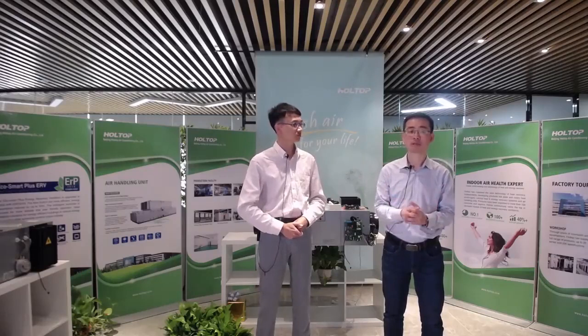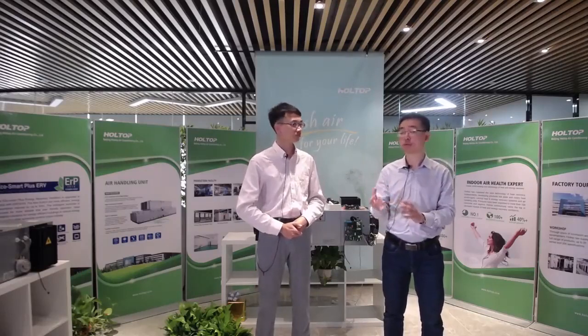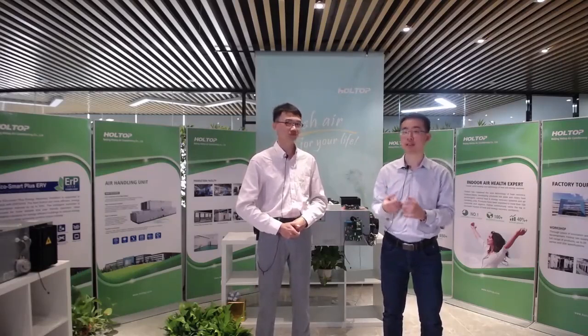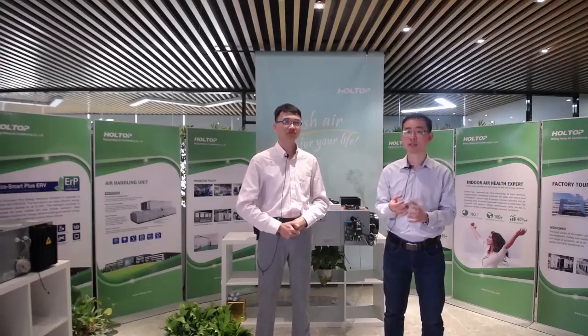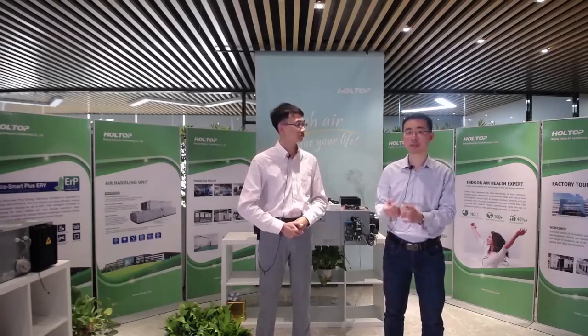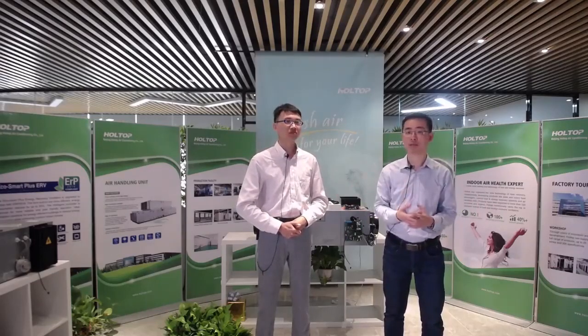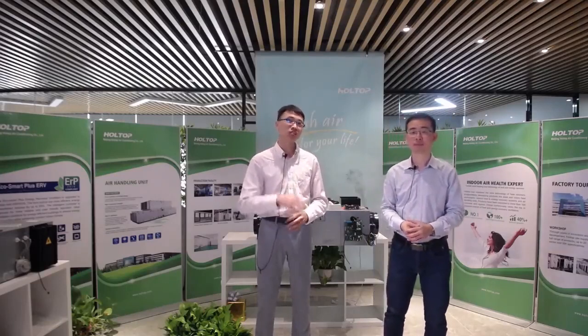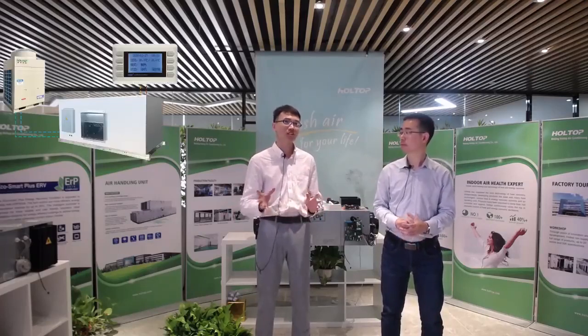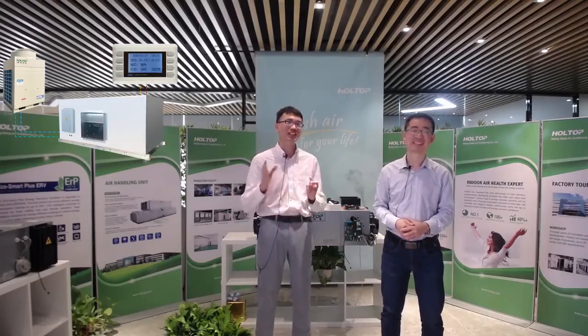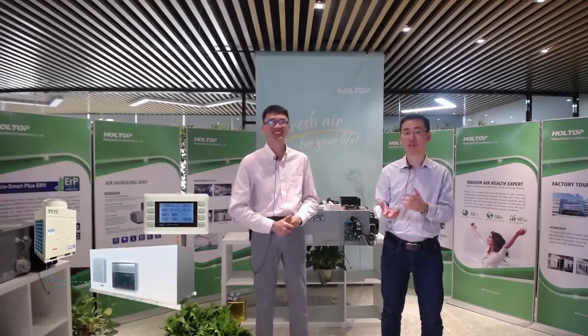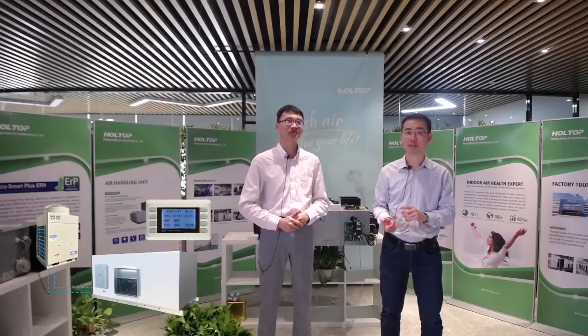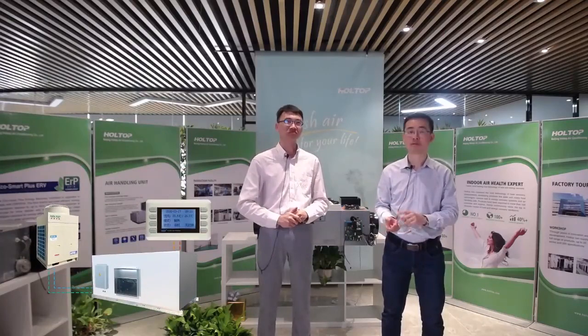The next one is the control. Holtop's condensing unit is equipped with new technology. We call it HMI, the controller, with SMD technology to get stable performance. And with intelligent defrosting, the logic will correct the values of data during outdoor condensing operation at low temperature. Yes, as I know, the control system is very important for a direct expansion system, because a direct expansion system is a very sensitive system that needs a lot of care. Yes, we have a high pressure alarm and full defrost phase protection.